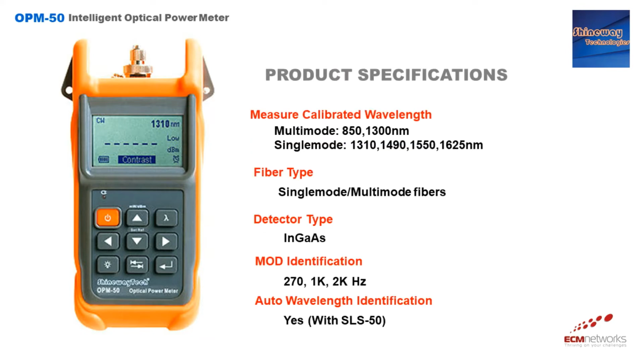Specifications of OPM50. It can measure calibrated wavelengths of 850 and 1300 nanometer for multimode fibers, and 1310, 1490, 1550, and 1625 for single-mode fibers. It uses an indium gallium arsenide detector. It can identify modulated optical signals of 270 Hz, 1 kHz, and 2 kHz. And if SLS50 is used as the optical light source, it will automatically identify the wavelength being transmitted.